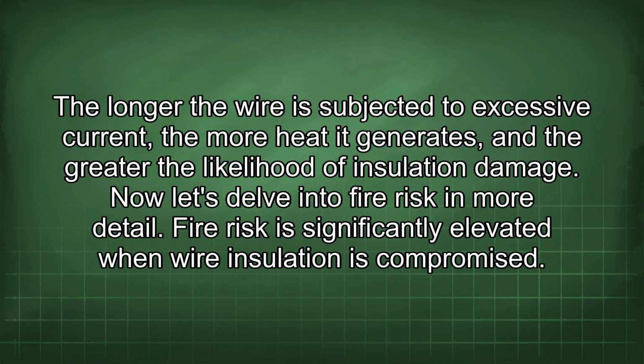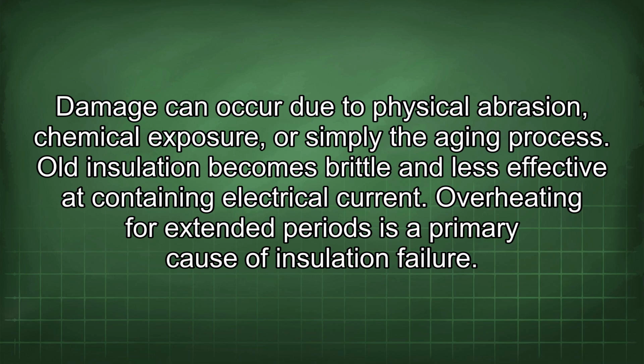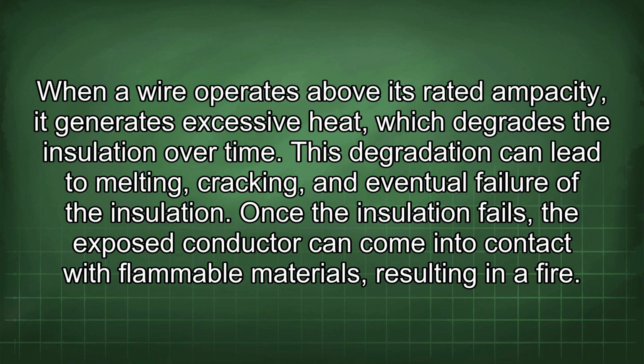Fire risk is significantly elevated when wire insulation is compromised. Damage can occur due to physical abrasion, chemical exposure, or simply the aging process. Old insulation becomes brittle and less effective at containing electrical current. Overheating for extended periods is the primary cause of insulation failure. When a wire operates above its rated ampacity, it generates excessive heat, which degrades the insulation over time. This degradation can lead to melting, cracking, and eventual failure of the insulation. Once the insulation fails, the exposed conductor can come into contact with flammable materials, resulting in a fire.